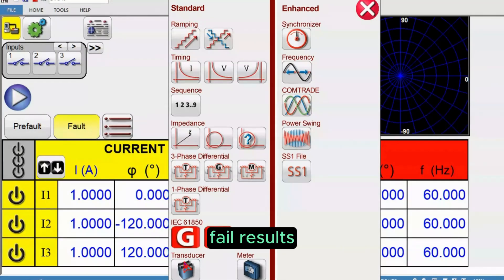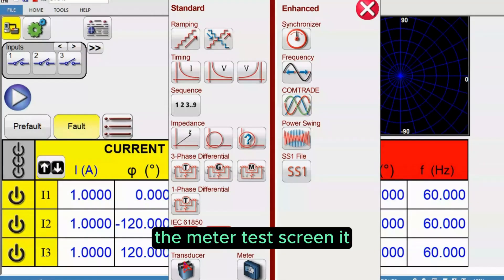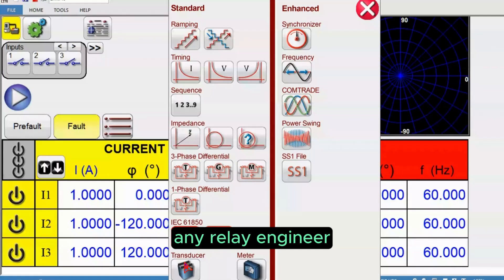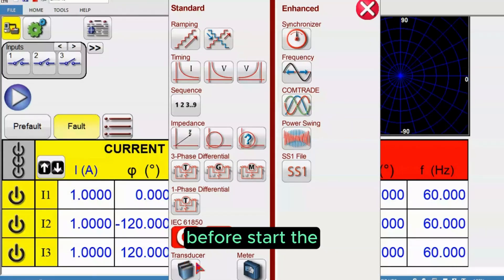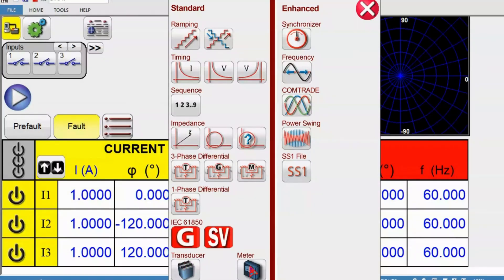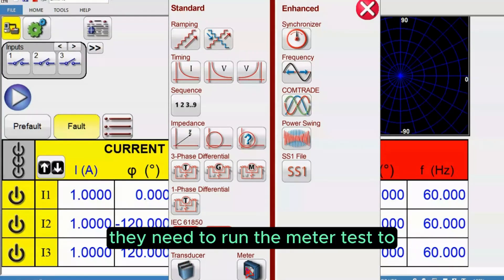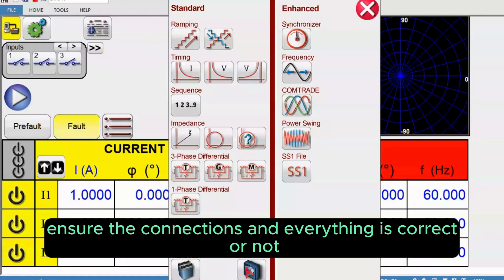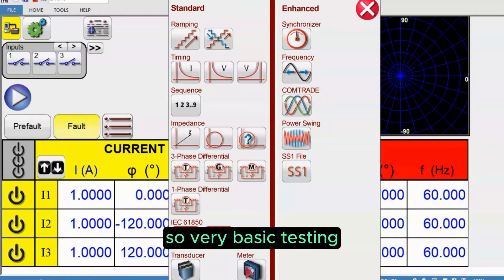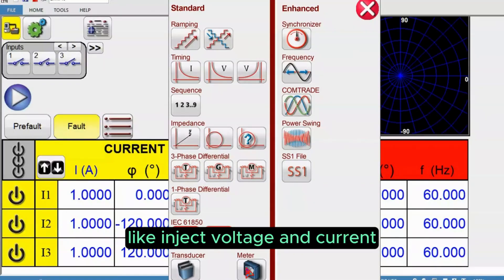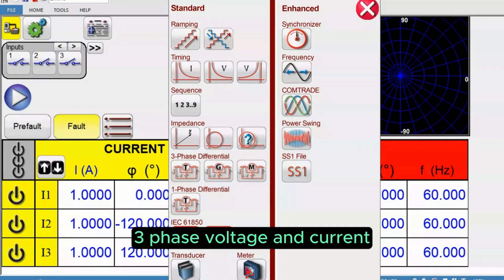The meter test screen. Any relay engineer before starting any testing needs to run the meter test to ensure the connections and everything is correct. It's a very basic testing. Users can use this meter test screen to inject voltage and current, three-phase voltage and current.